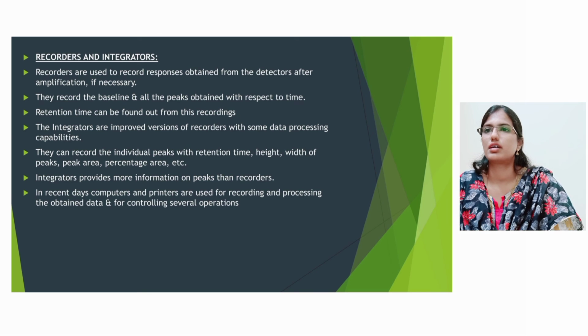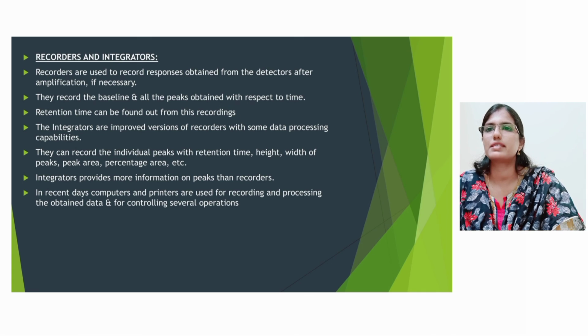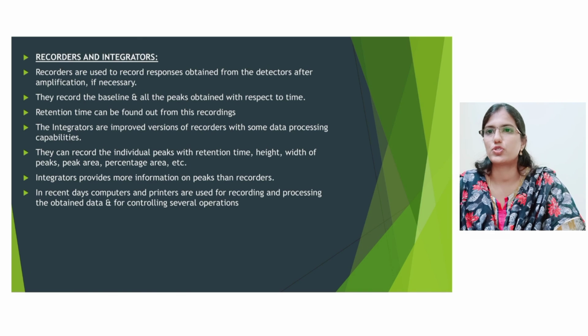Recorders and integrators. Recorders are used to record responses obtained from the detectors after amplification if necessary. They record the baseline and all the peaks obtained with respect to time. Retention time can be found out from these recordings. The integrators are improved versions of recorders with some data processing capabilities. They can record the individual peaks with retention time, height, width of peak, peak area, percentage area, etc. Integrators provide more information on peaks than recorders. In recent days, computers and printers are used for recording and processing the obtained data and for controlling several operations.